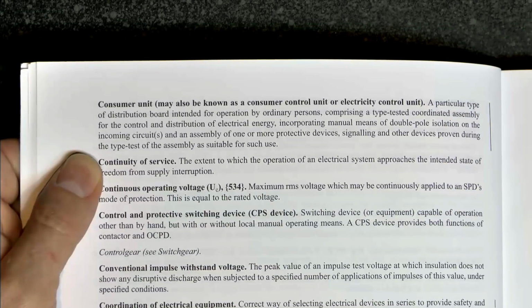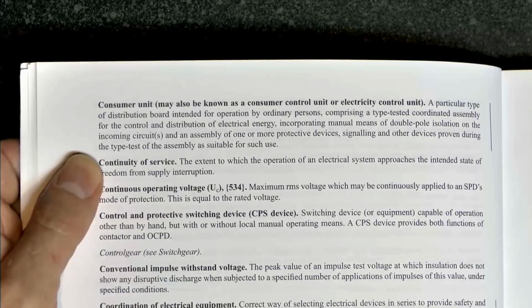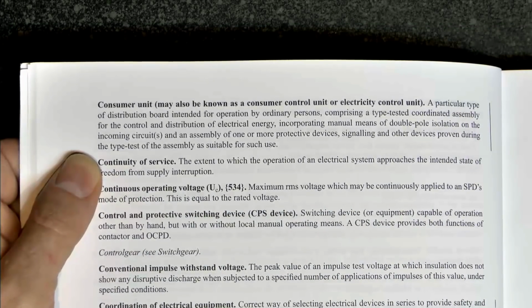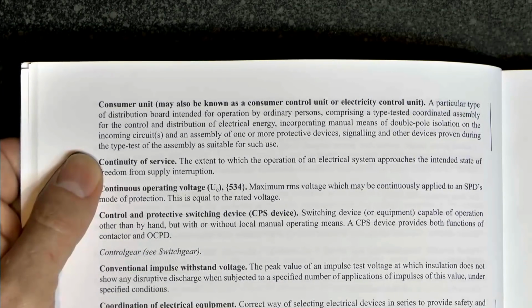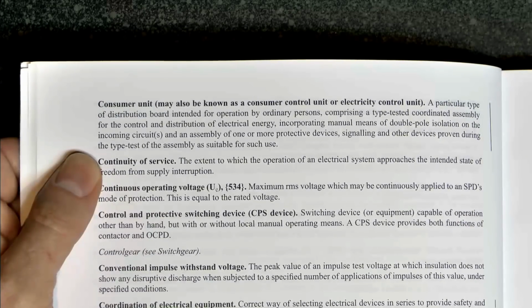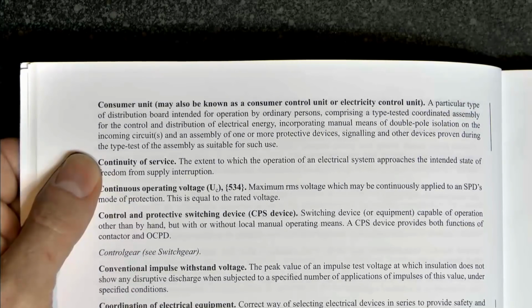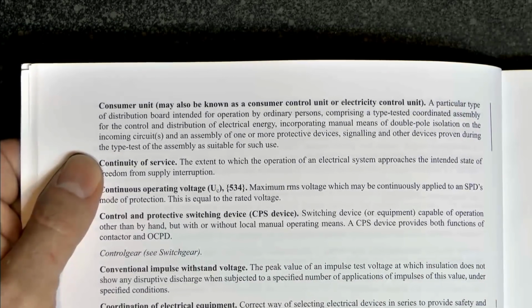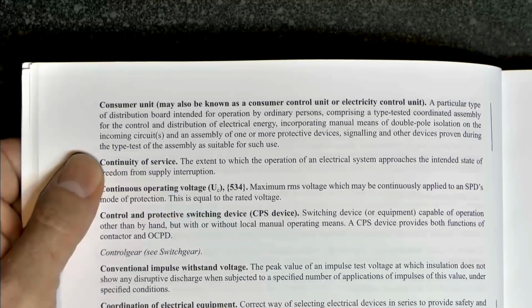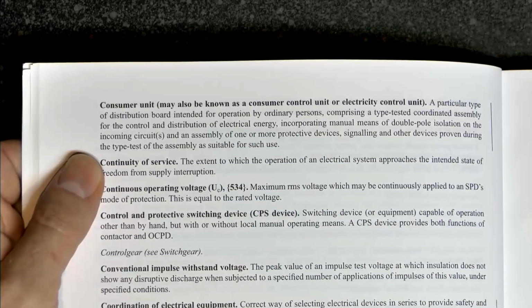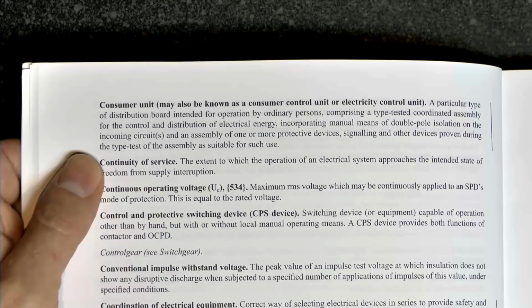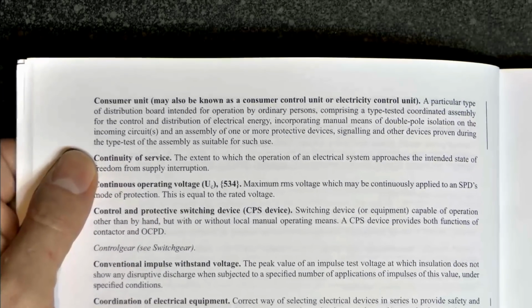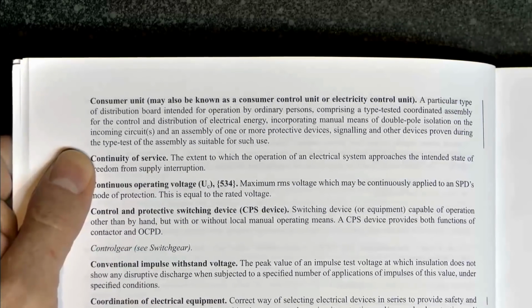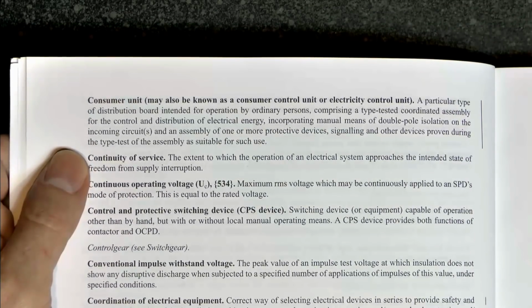You could put a consumer unit in any other kind of property or premises. The section about it being a type-tested coordinated assembly means that if you buy a consumer unit from a particular manufacturer, in order to remain type-tested, you have to install devices from that same manufacturer in it. You can't put another manufacturer's circuit breaker into someone else's consumer unit, because then it's not a type-tested coordinated assembly anymore - someone else's circuit breakers won't have been tested in it. They may well work, but that's not the point - it's not a type-tested assembly. So in theory, if you bought a consumer unit and then mixed in circuit breakers from another manufacturer, it's not a consumer unit anymore. An interesting change to the definition there, and again, you can put them in places other than domestic premises.